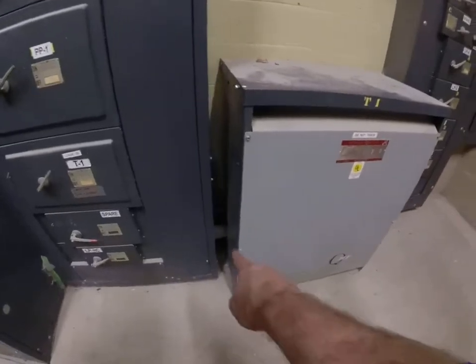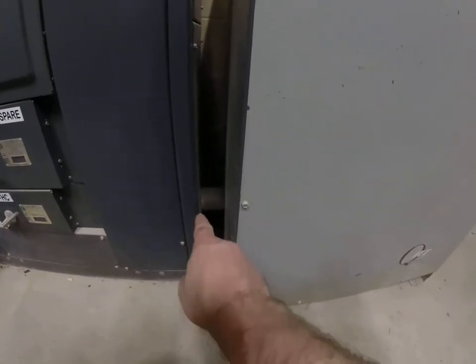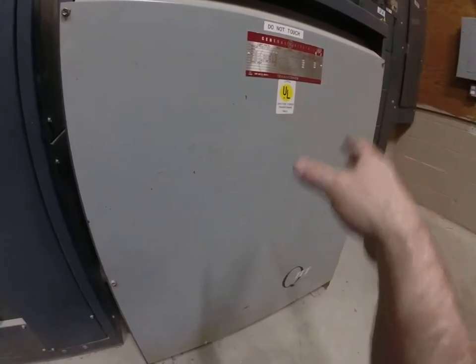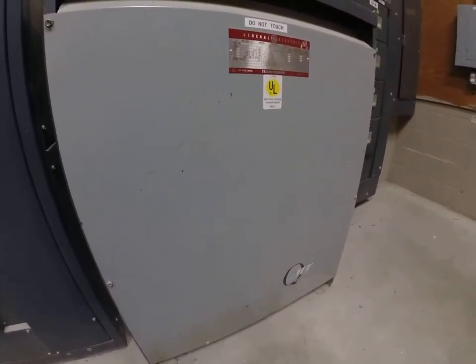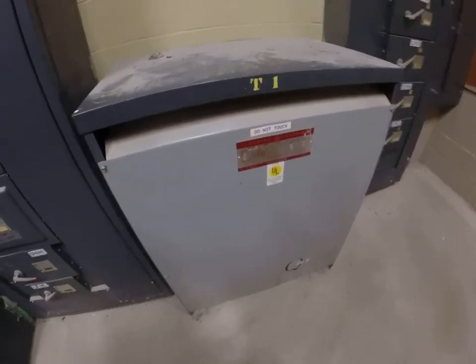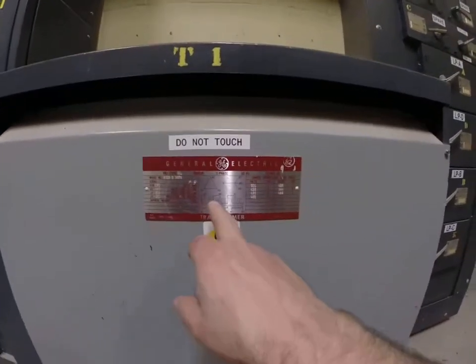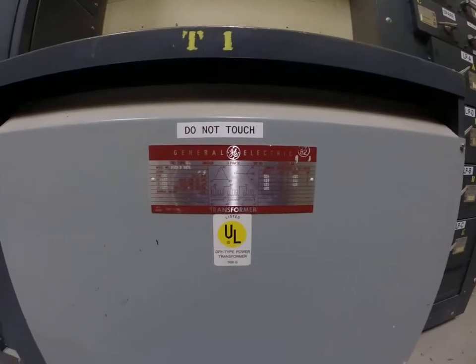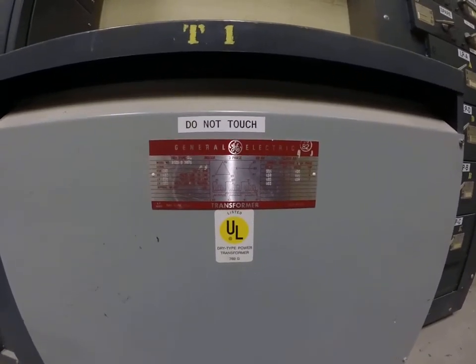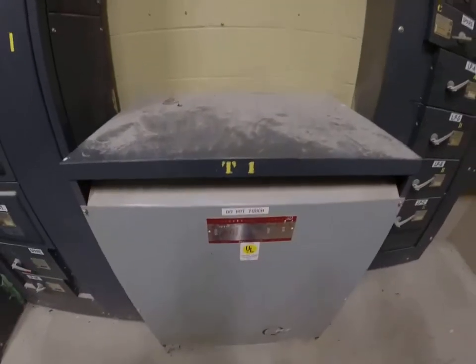So you notice that there's a nipple in here between the 2 pieces of gear. You've got 480 volts 3-phase, probably delta, coming into this transformer. That then steps this down to a usable voltage for lighting, 208/120. You can see the nameplate on here. We've got delta and Y. Typical to commercial installations. This is T1.